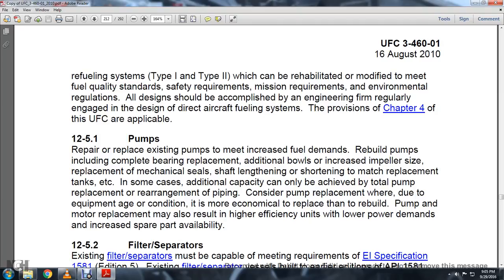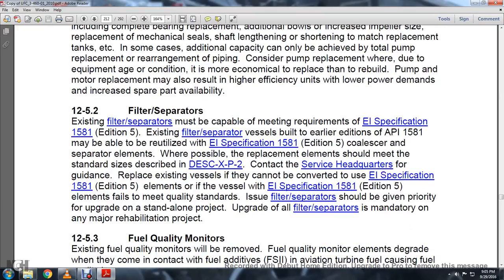Section 12-5-1: Pumps. When replacing existing pumps to meet increased fuel demands, refueling upgrades may include complete bearing replacement, additional bowls, increased impeller size, replacement mechanical seals, and shaft length adjustments. In most cases, additional capacity can only be achieved with a total pump replacement and rearrangement of piping. Consider pump replacement where the equipment condition makes it more economical to replace than rebuild the pump. Most replacements must also address increased availability of spare parts.